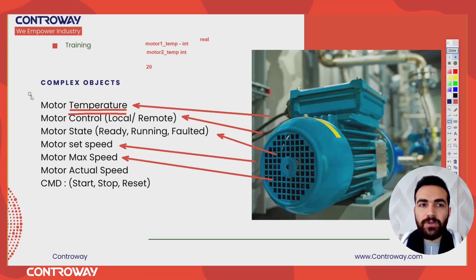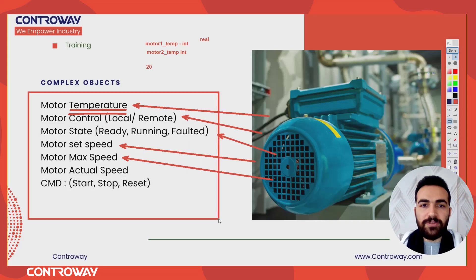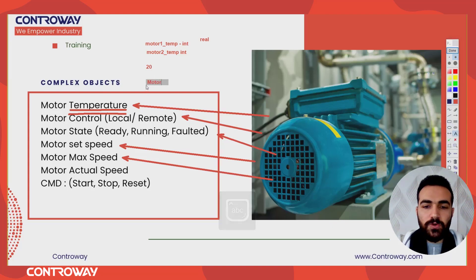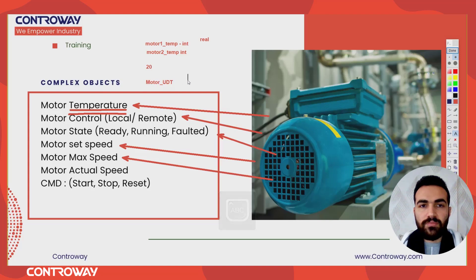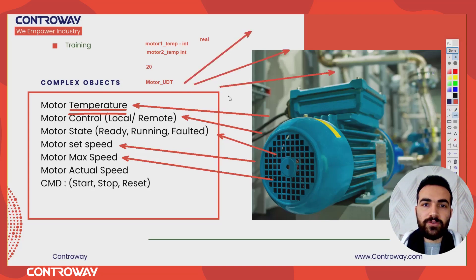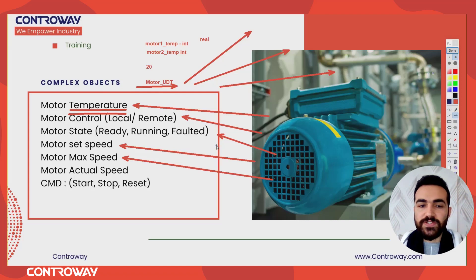So why not make something simpler? We make a package — a special type of data — that includes all these variables and we give it a name like 'Motor UDT'. Then I make copies of this data type: the first one, the second one, the third one — up to 20 times. If I need to update anything inside this data type, it will be updated automatically. We will see how to do this in TIA Portal.